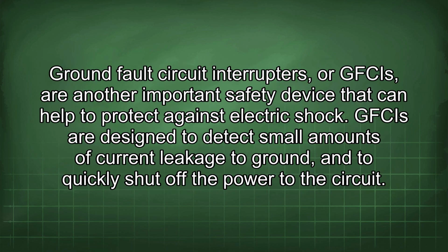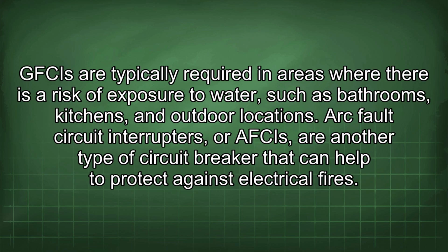Ground fault circuit interrupters, or GFCIs, are another important safety device that can help to protect against electric shock. GFCIs are designed to detect small amounts of current leakage to ground, and to quickly shut off the power to the circuit. GFCIs are typically required in areas where there is a risk of exposure to water, such as bathrooms, kitchens, and outdoor locations.